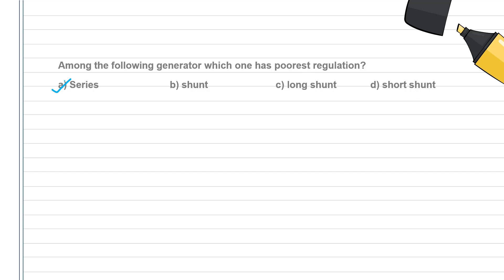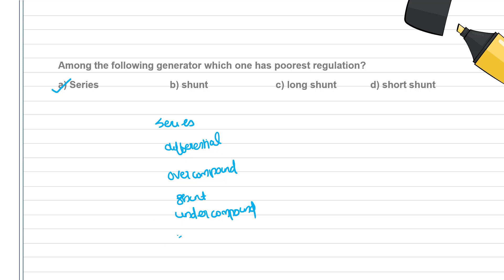The regulation order from poorest to best is: series (poorest), then differential compound, then over-compound, then shunt, then under-compound (best regulation). The poorest regulation is the series generator, and the best regulation is the under-compound generator.